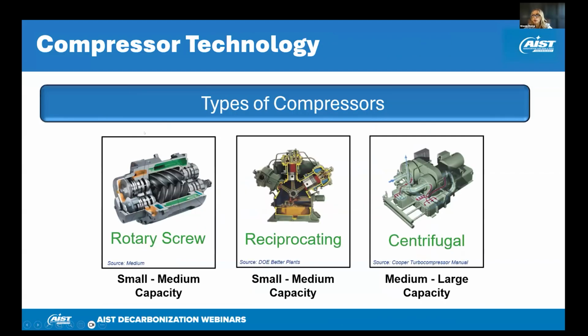When you walk through the mill, you typically find three different types of compressors. We have rotary screw style compressors, we have reciprocating, and centrifugal compressors. They're all good for different applications, different flow ranges. Some are oil flooded, such as the rotary screw in most applications. In the reciprocating, that means that there's oil in the compression chamber, and that gets filtered and delivered to the process. With the centrifugal, that is oil-free by design, so there's no oil carryover in the process air.